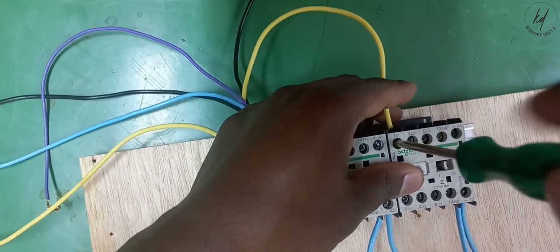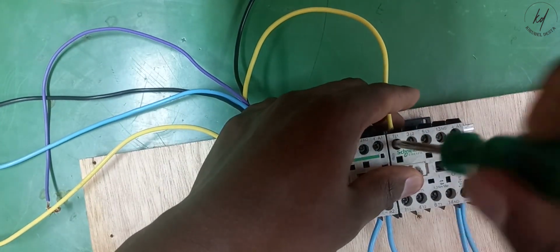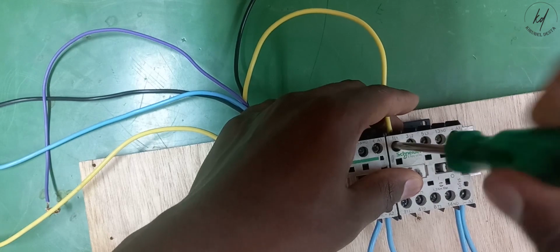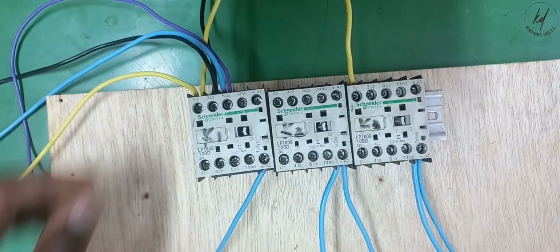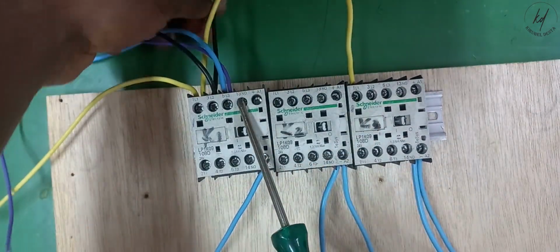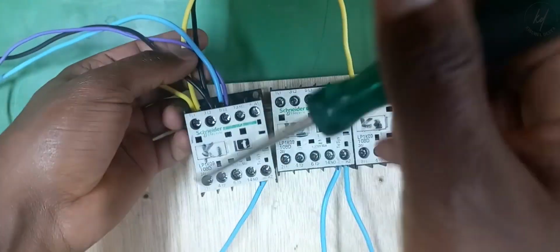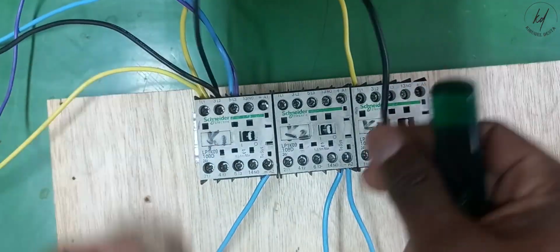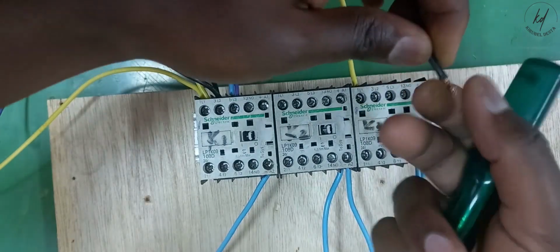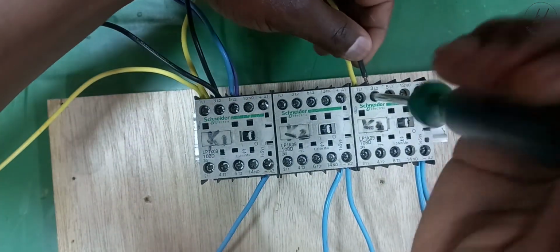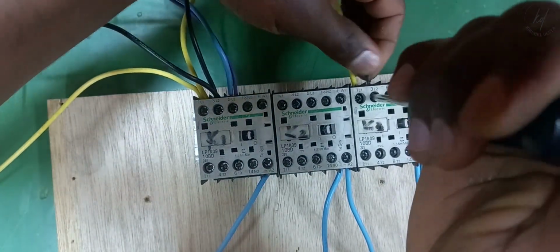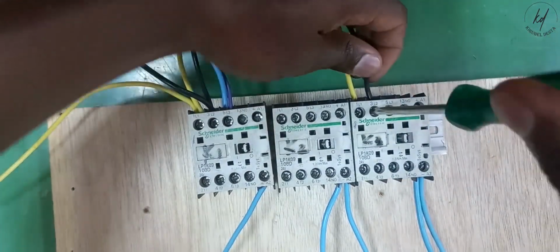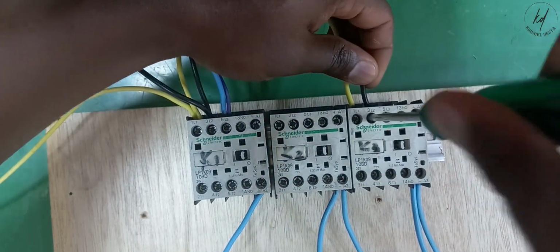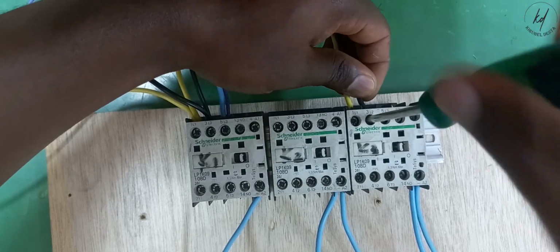The Star Delta starter includes a control circuit that typically consists of a timer, contactors, and overload relays. When the motor is started, it is initially connected in a Star configuration to reduce the starting current, which can be up to 6 times the motor's full load current. After the motor reaches a specific speed, the timer switches the winding connection to a Delta configuration to ensure the motor operates efficiently.